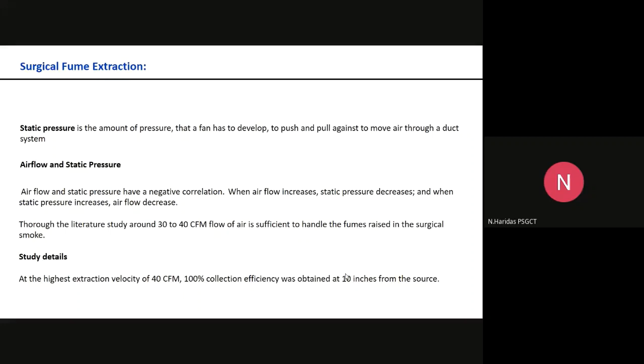Through various literature studies, it was found that around 30 to 40 cfm of airflow is sufficient to handle the fumes raised in the surgical smoke. At the high extraction velocity of 40 cfm, 100% collection efficiency was observed from the source if it is at a distance of 10 inches from the suction.